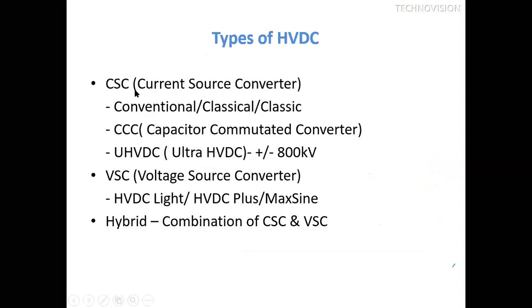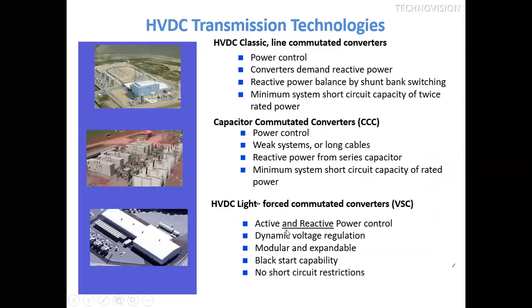Based on these, we have some types of HVDC, that is current source converters, voltage source converters, and hybrid HVDC. It's a theoretical aspect. There are many benefits of these systems. HVDC Classic is generally used for bulk power transmission. When the short circuit ratio of the system is less than 3, then CCC is used. When the short circuit ratio is, we can say, 0 also, then voltage source converter technology is used.